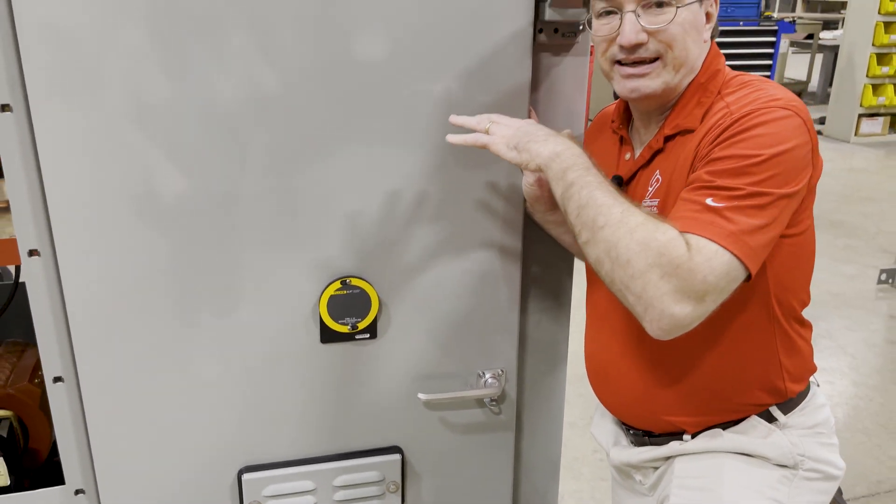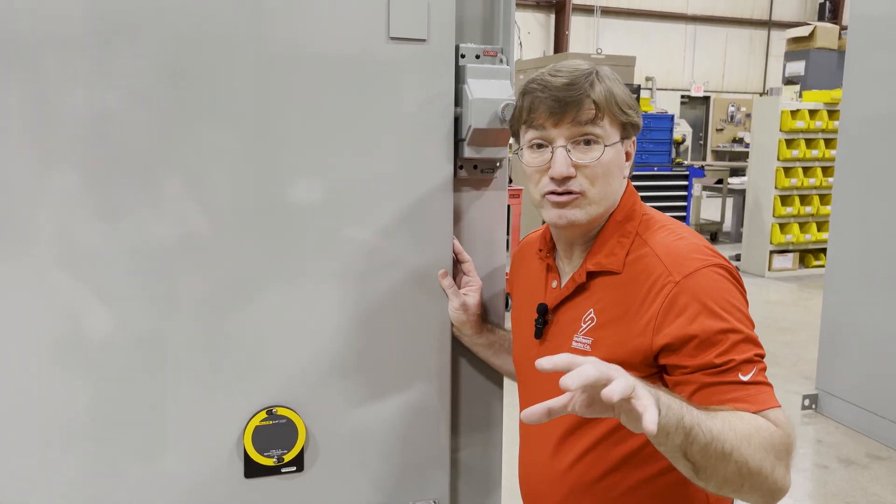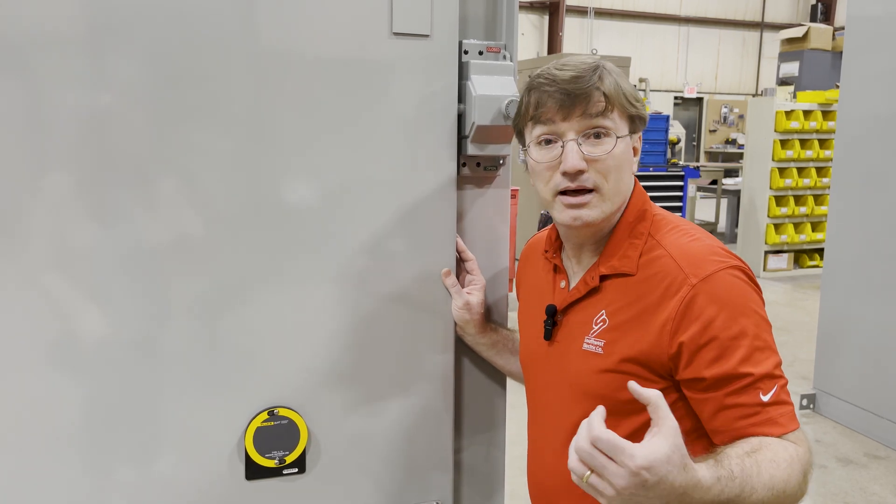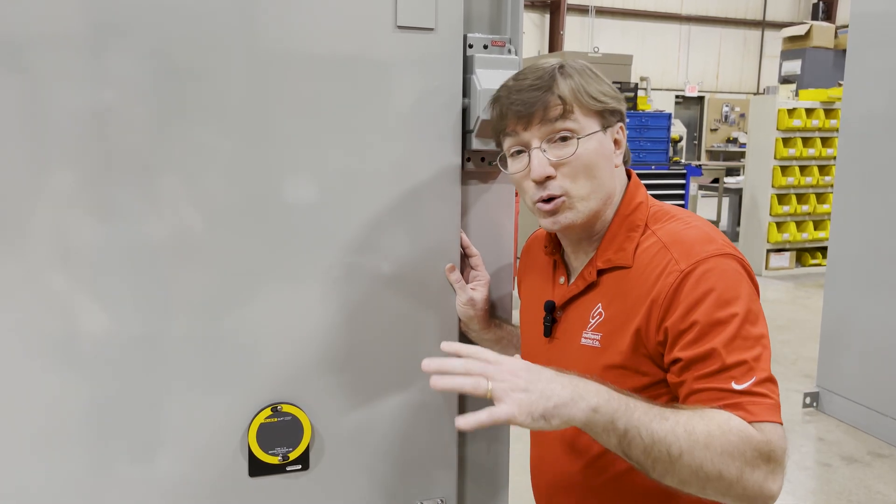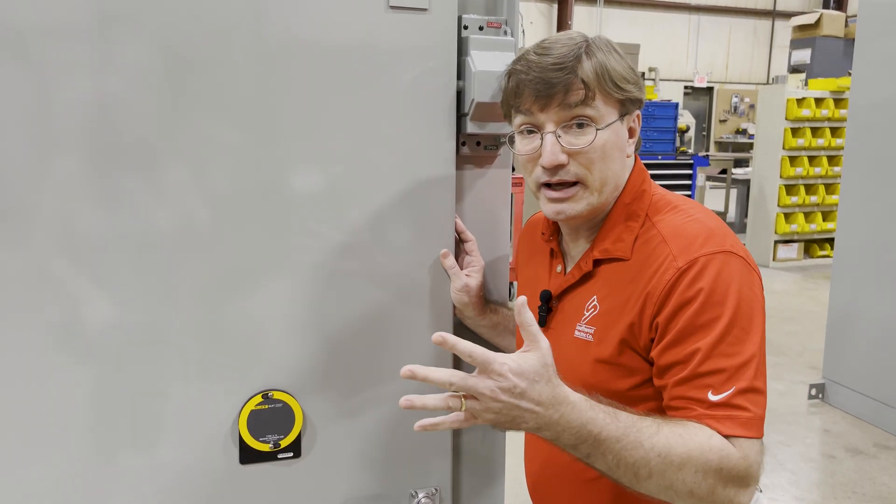They allow you to see inside the switchgear while it's energized and look at your cable connections, your bus connections, to see if all your joints are healthy, if they're passing current correctly, or if any hotspots are developing. If a hotspot develops, it could end up into a fault.